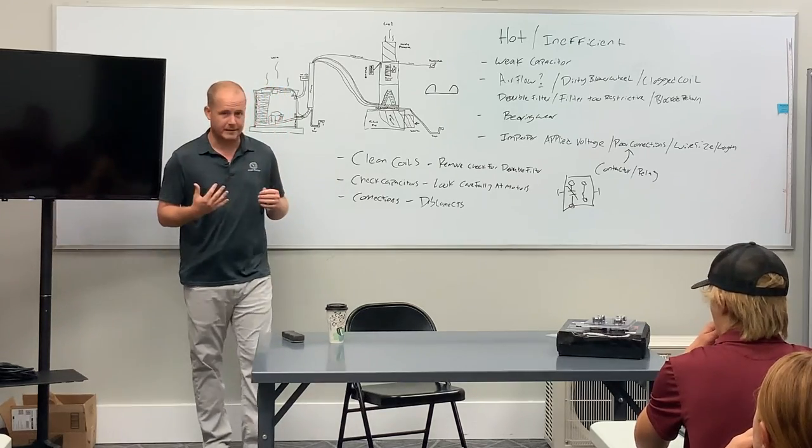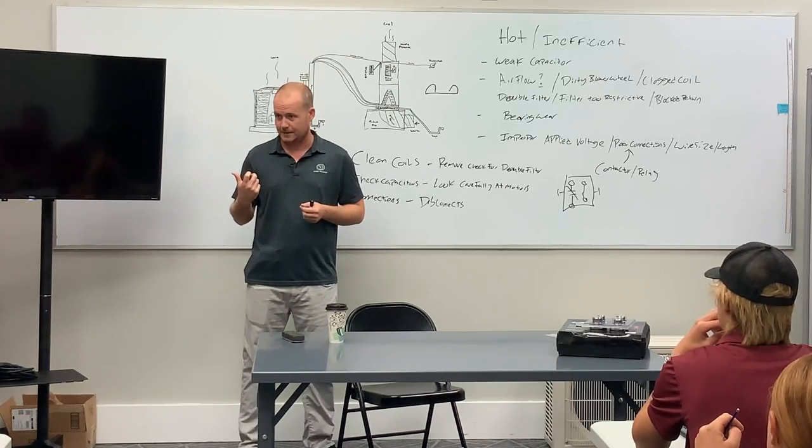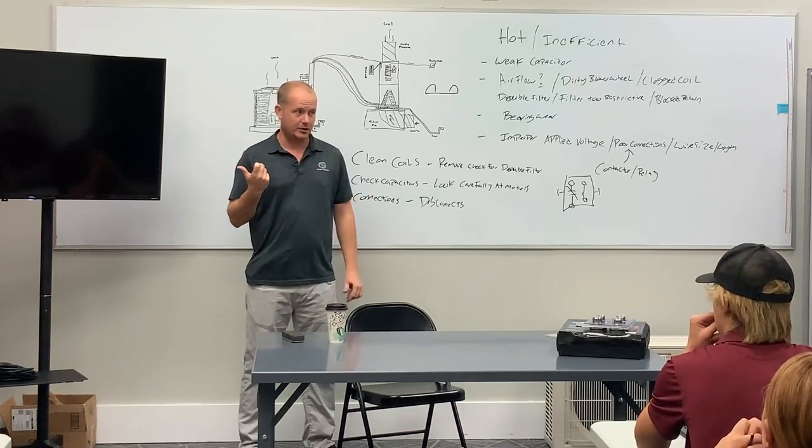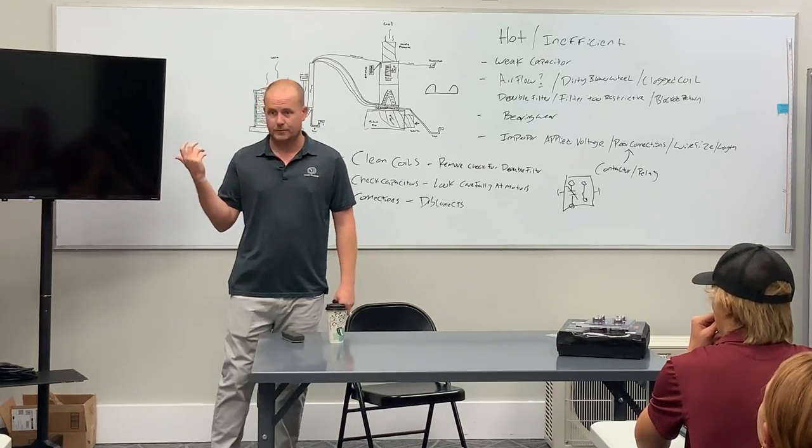And there are a couple of things with disconnects. The number one and the easiest is the actual pull itself. If it's a pull disconnect, and that pull has damage on it, and where it goes in has damage on it, then the disconnect should be quoted.